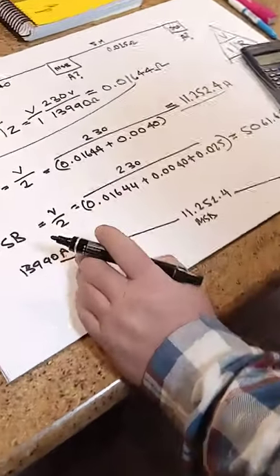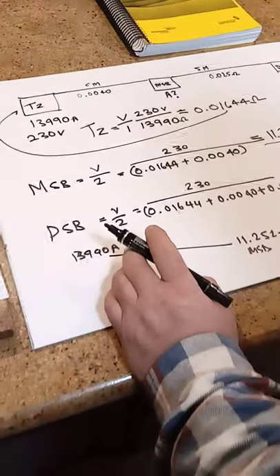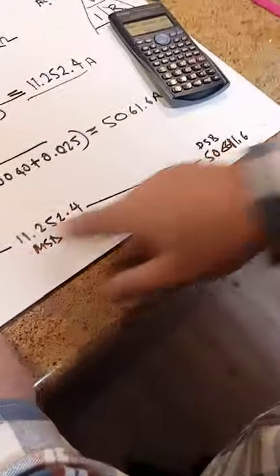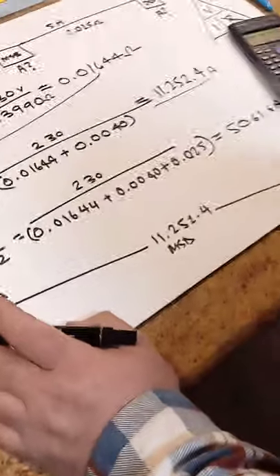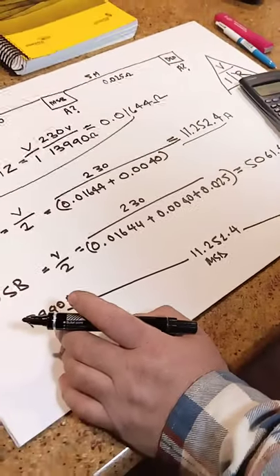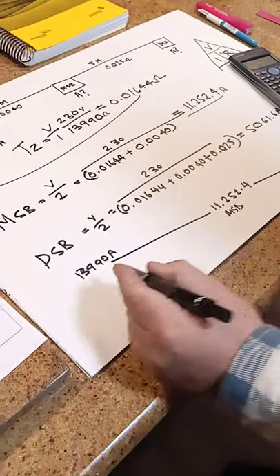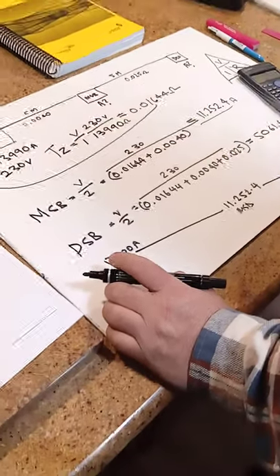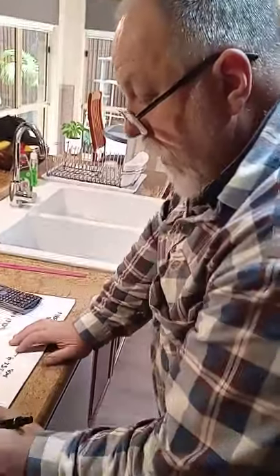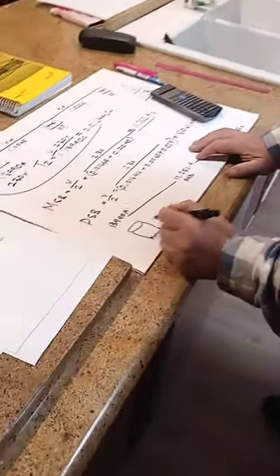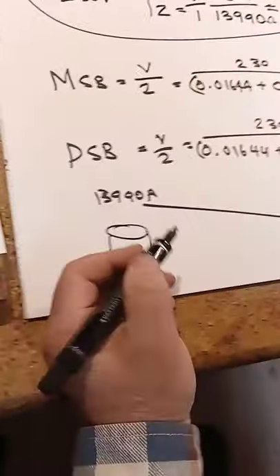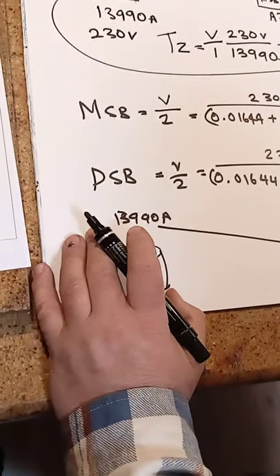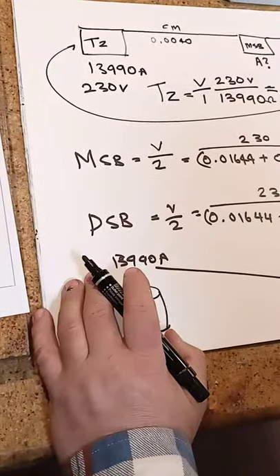If you look under the SIR book, and that's the only place you'll find it for Victoria, the minimum size circuit breakers that we're allowed in Victoria are 6KA, and this actually comes under the 6KA. But the idea is to show you that when you look at your circuit breaker and you've got the 20 amp on there and a 6KA or a 10KA, that's the KA rating we get on our circuit breakers. On HRC fuses, which are made of ceramic, they all go to about 80KA. And the difference is because you've got ceramic casing versus basically you're looking at a coffee cup versus a plastic cup. A plastic cup's going to melt with a lot more heat quickly compared to a ceramic cup.